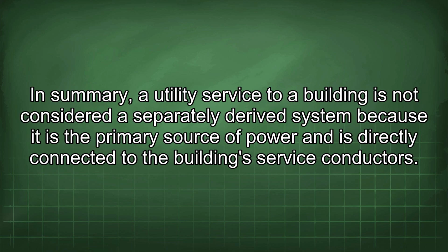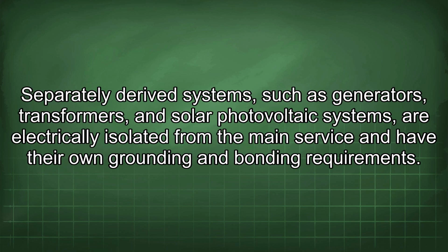In summary, a utility service to a building is not considered a separately derived system because it is the primary source of power and is directly connected to the building's service conductors. Separately derived systems, such as generators, transformers, and solar photovoltaic systems, are electrically isolated from the main service and have their own grounding and bonding requirements.